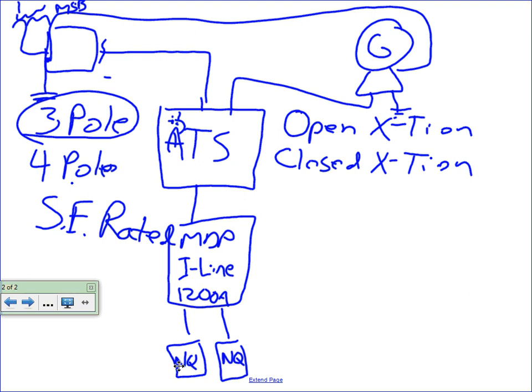But the code requires, well, let's move them off. The code requires an emergency system of a building to be what they call selectively coordinated. The definition of selective coordination is the device closest to the fault has to take that fault out. So to us, that means fully coordinated. Every device in that system has to be coordinated.